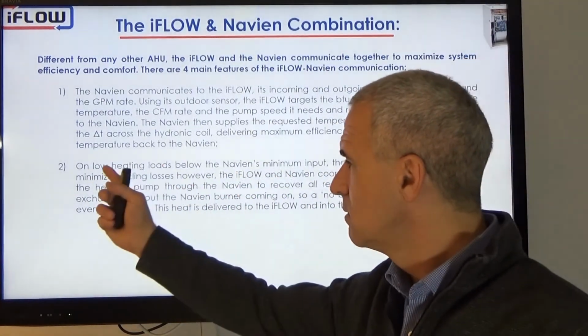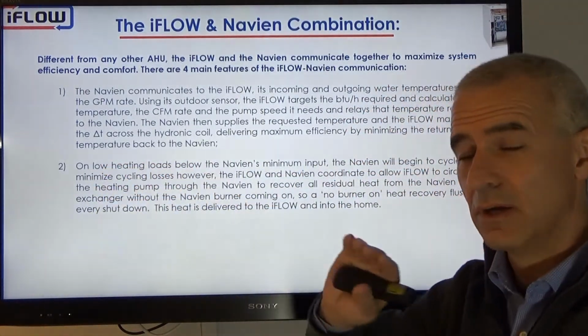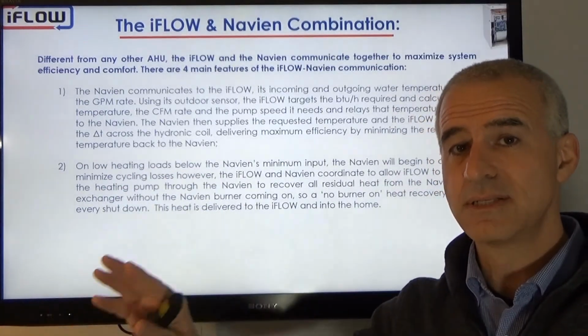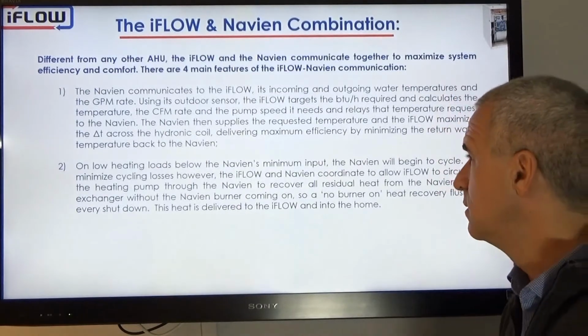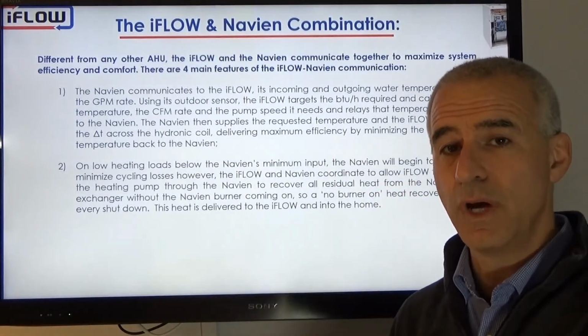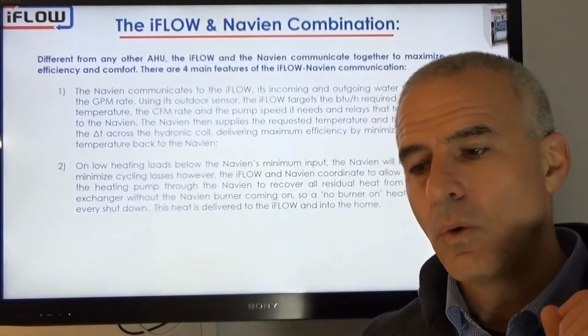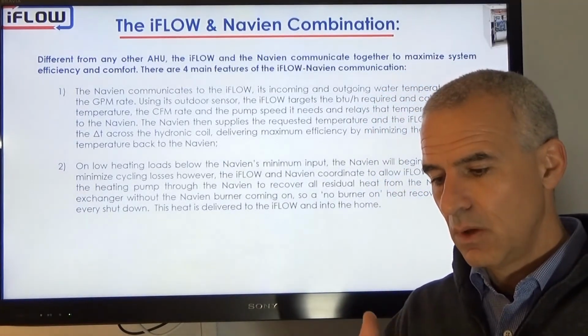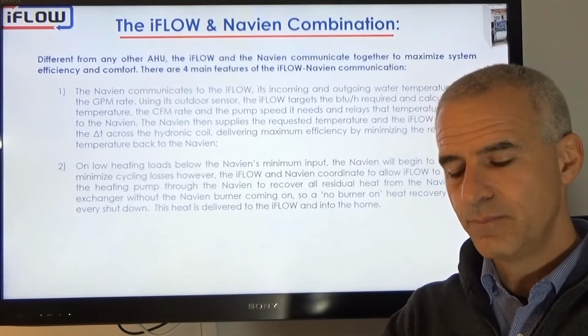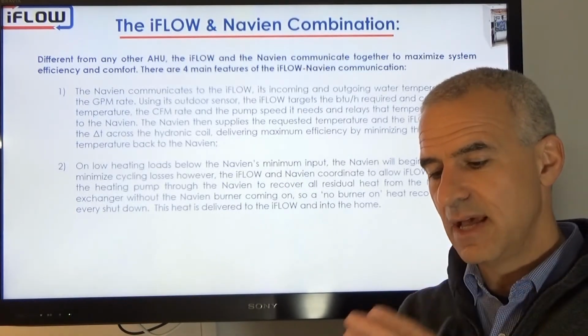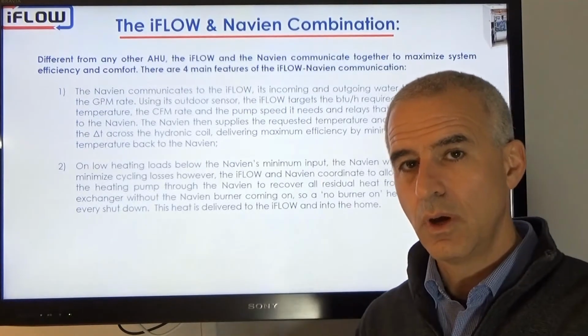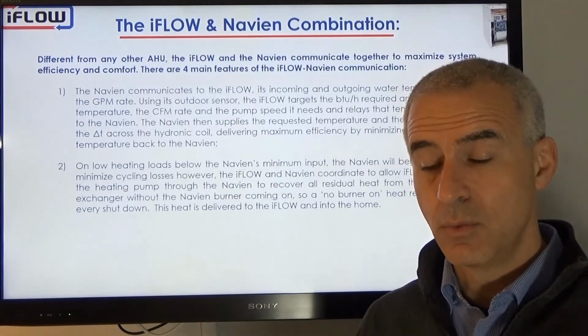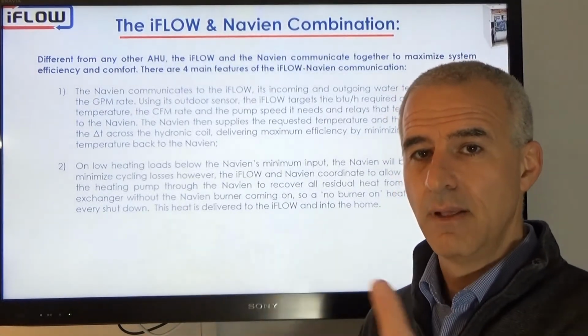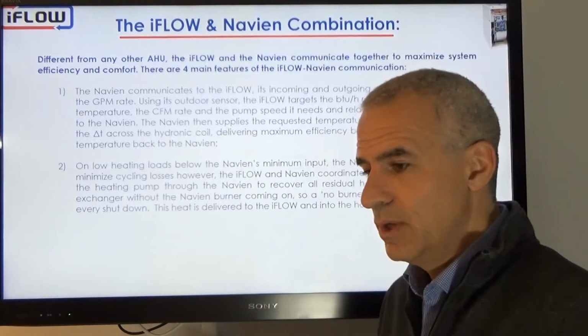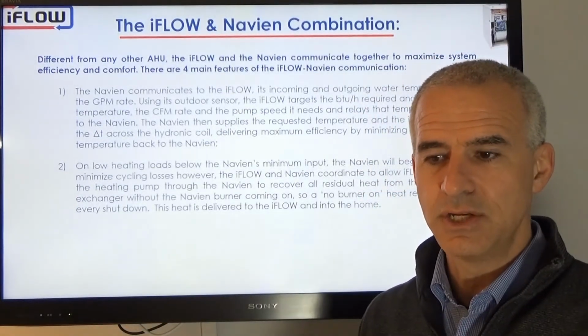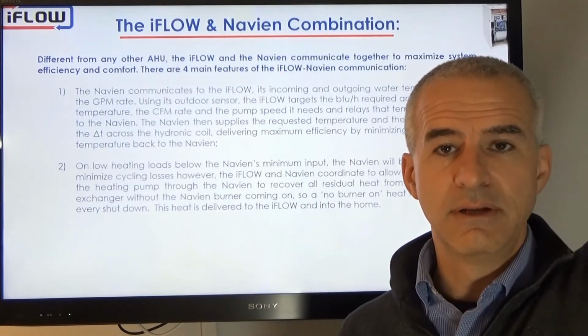On the low heating loads, right, on loads below the Navien's minimum input, so let's say an 8,000 BTU load or a 6,000 BTU load, the Navien has no choice but to cycle as well. But here's what we do. When we are in a heating call and the Navien needs to cycle off, the iFLOW tells the Navien, hey, we're in a heating call, so I'm going to continue to run my pump. So we continue to flow the pump through the Navien, but we don't fire the burner. And what we do is we scrub all the BTUs out of the Navien heat exchanger, deliver it into the iFLOW heat exchanger, deliver it into the coil, into the house.